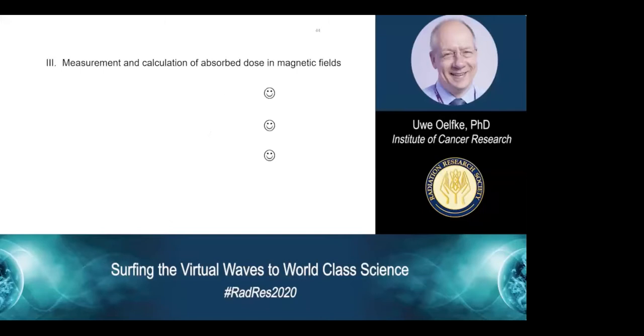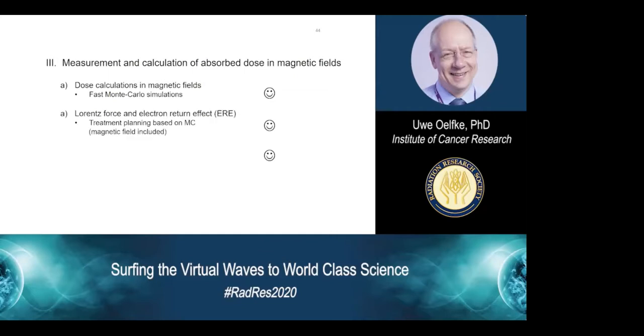Let's now summarize this short section about measurement and calculation of absorbed dose in magnetic fields. First, the dose calculation in magnetic fields has been solved by fast Monte Carlo simulations. And these new dose algorithms are then used in treatment planning programs, and they account for the Lorentz force and the electron return effect in patients, and that has been tested for a number of clinical indications. And finally, also for dose measurements, not only relative but also absolute measurements, this problem has been solved in magnetic fields through modified protocols and correction factors, and there was a huge international effort to establish new dosimetry protocols in strong magnetic fields.